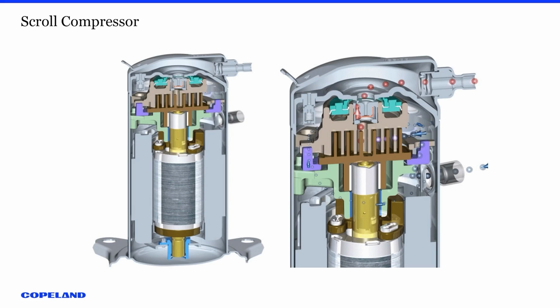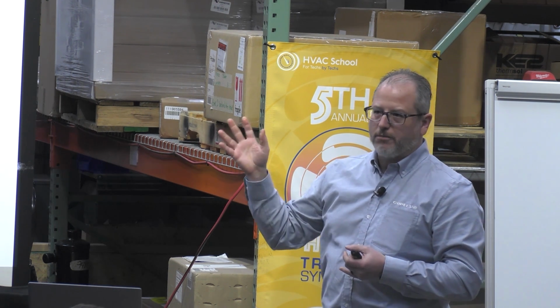So on the left, our bottom bearing should always have oil. It should be in oil in there. And I'll show in a second what that crankshaft and everything looks like. But it brings oil with centrifugal force to the top to lubricate all the parts and pieces inside that compressor. Okay? The only scroll compressor where we use an actual pump for the oil, a positive displacement pump, would be the variable speed.